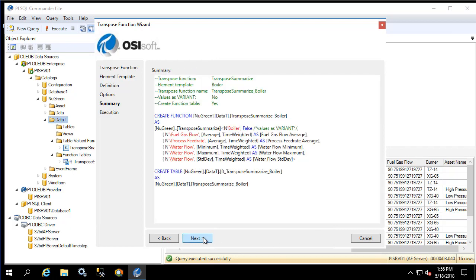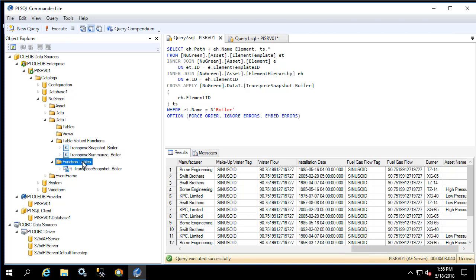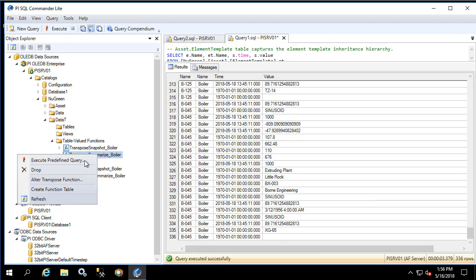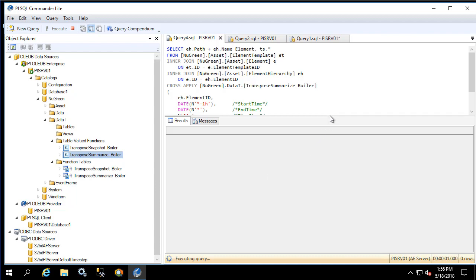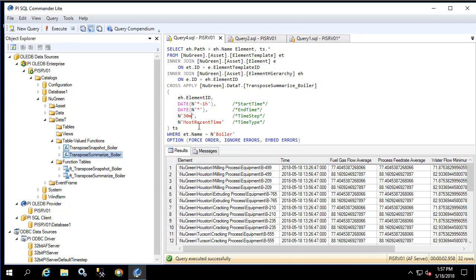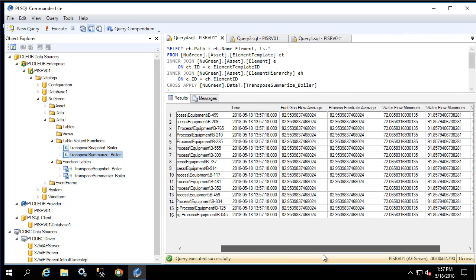We'll click Next and create the transpose function. Now let's query the summarize table for the boiler. The predefined query uses a one-hour time range with 30-minute time steps so we see two rows per element. Let's change this to only one row. Notice here that we have 16 rows — one for each element — and we have the average of both the fuel gas flow and the process feed rate, as well as the water flow min, max, and standard deviation for the last hour.